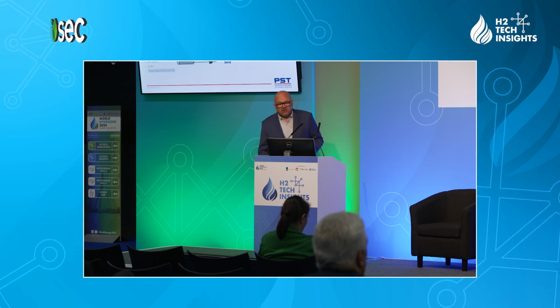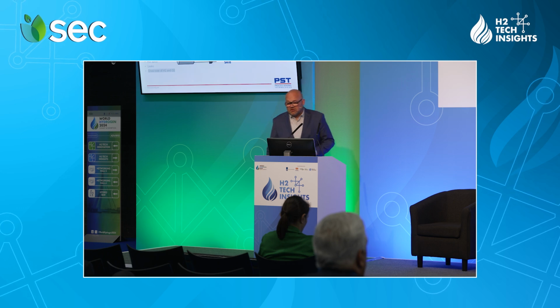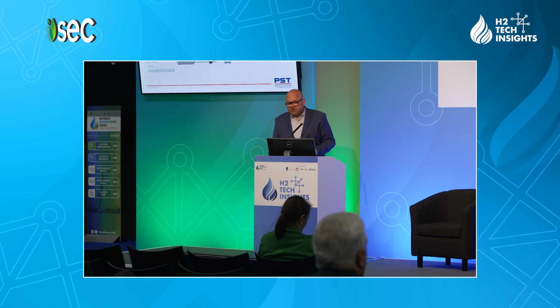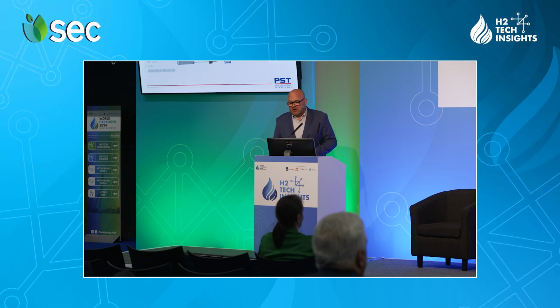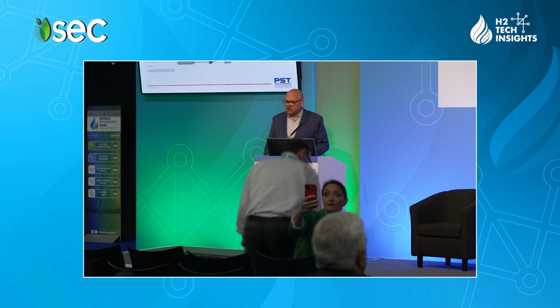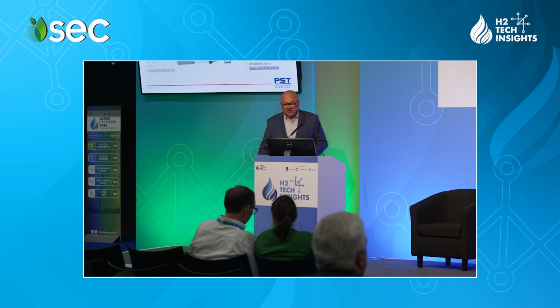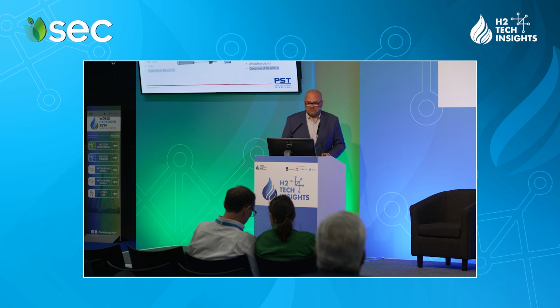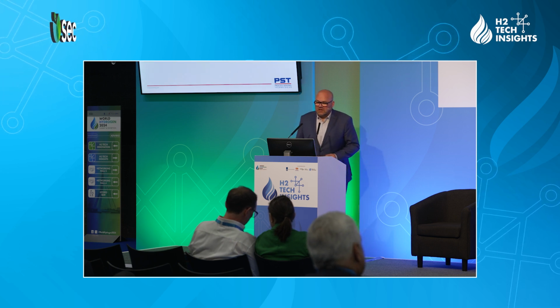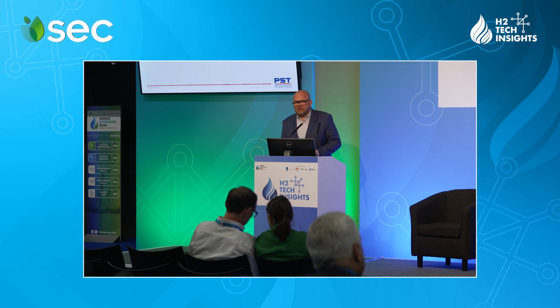At the separation skid, there is a lot of material there, of course. The heat exchangers we just saw, valves, pumps, all kinds of sensors measuring the process and controlling it. Maybe level controls which are not stable, corrosion, hydraulic shortcuts, insufficient purges. Same kind of implications, especially the crossover of hydrogen and oxygen. So analysis, you could consider that the last defense for safety.